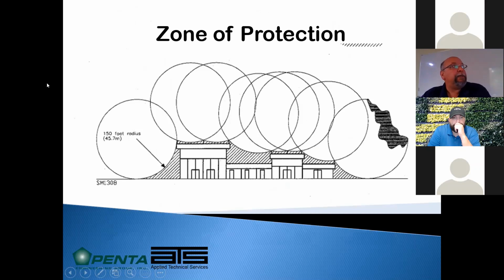So I mentioned the zone of protection. If you imagine a 150-foot radius sphere, a big ball sitting on top of the building, from one air terminal to another, we roll that ball around on the roof, resting it on top of the air terminals. And if we have a lower section of the roof, like between a penthouse and the parapet wall, anything on that roof that does not breach the curvature of that sphere falls within a zone of protection, and it doesn't need air terminals or lightning rods on it. Sometimes lower roof edges that jut out may be covered and not need lightning protection, but if you have a lower roof edge that juts out far enough, you do need additional protection on that lower roof level.